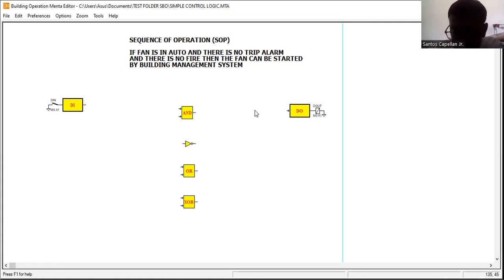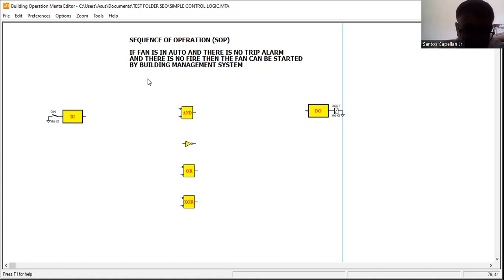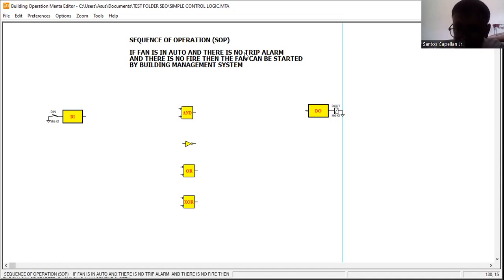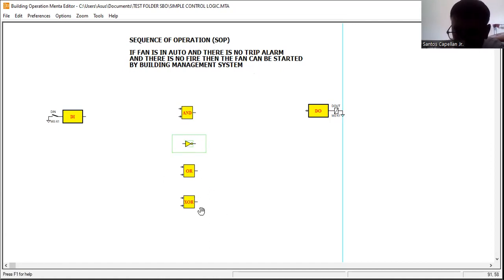Based on the simple logic gates, how are we going to start the fan? I'm showing you input blocks — digital input — and an output block — digital output — meaning we will be controlling this fan. The sequence of operation: if the fan is in auto and there is no trip alarm and there is no fire, then the fan can be started by the building management system. This is a very simple sequence of operation. The logic gates we will need here are the AND gate, the NOT gate, and we will see if we will also use exclusive OR and OR gates.